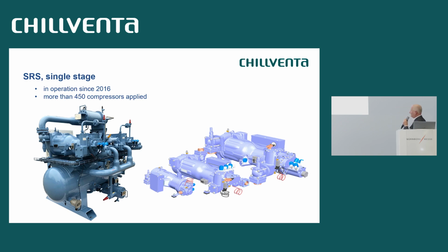So this is our range of SRS, semi-hermetic, single-stage screw compressors. You see they come with a whole lot of features like the solenoid valves, the oil filters, the pressure differential switches, and sensors. And they can easily be mounted onto horizontal oil separators. They are very compact and very versatile, so you could use single compressor applications, double and triple packs. They can be even compressors or uneven compressors. So you could have a very small one for your weekend and low capacity demand, and a big compressor which is then added for the operation during the week.